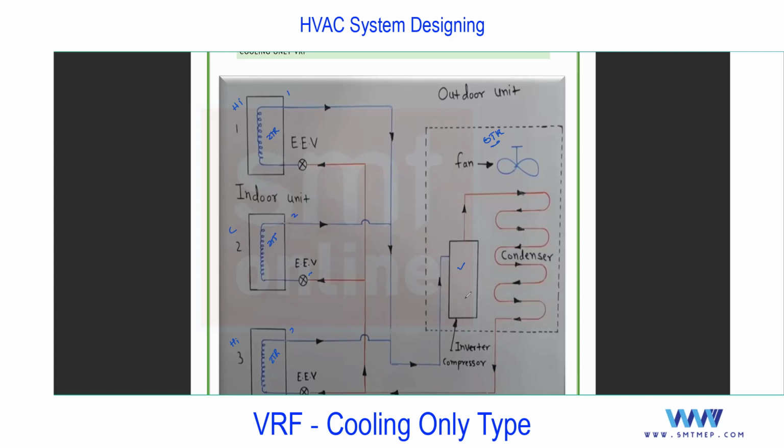So you see the cycle starts from the compressor. You know the cycle: compressor, then condenser, then expansion and evaporator. And the important point here, in a split system, in the new models, you know this, the expansion is in the outdoor unit, right? But in the VRF cooling only model, you'll find the expansion in the indoor only.